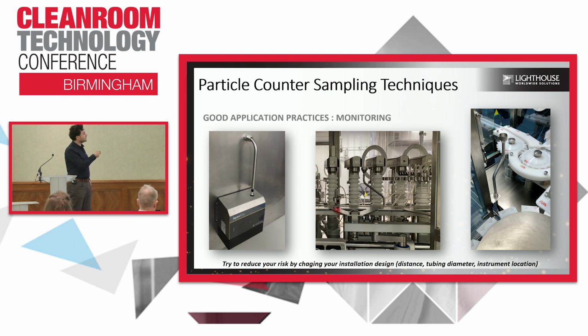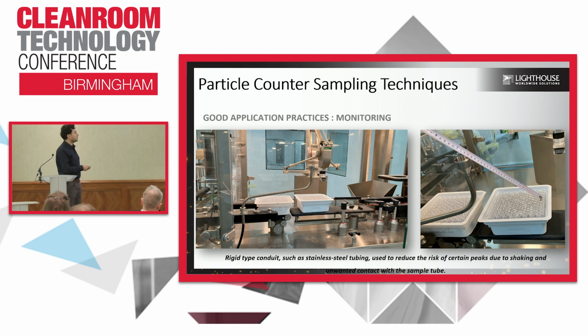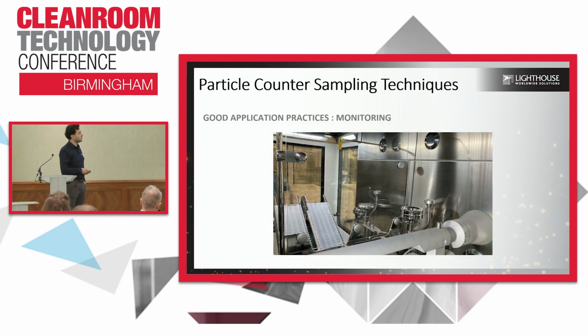And this kind of installation helps you, because operators can touch it, or the system will also have some vibration, so you are protecting your system with rigid conduits. Again, another point, you cannot really leave your particle counter on the surface because there are a lot of mechanical parts underneath. So we have this side installation with a special fixture, and we take it in with a very smooth turn so that the distance is within 30 centimeters from the risk location. Again, another special fixture. See, we have this tubing that comes in and supports itself to keep it at a certain distance, which is less than 30 centimeters in this example.